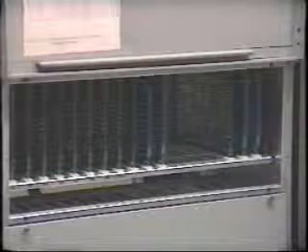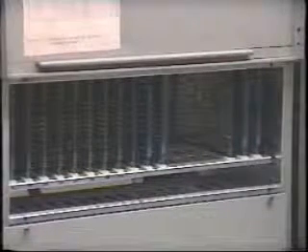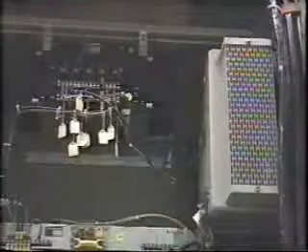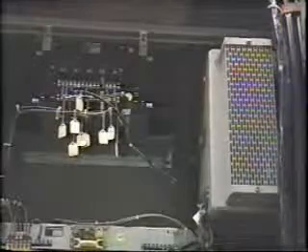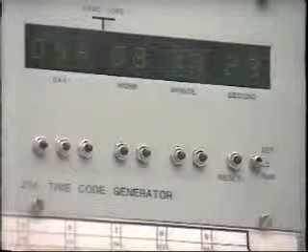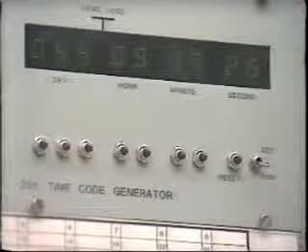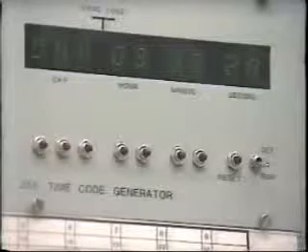In addition to the oscillograph machines themselves, there are several accessories that must be installed to complete the recording system. And these include starting sensors or triggers to start the recordings, signal conditioners to prepare the data for recording, power supplies and inverters to provide an uninterruptible power source for the oscillographs, and time clocks to keep track of the exact time of recording. The time log helps coordinate the output from many recorders.